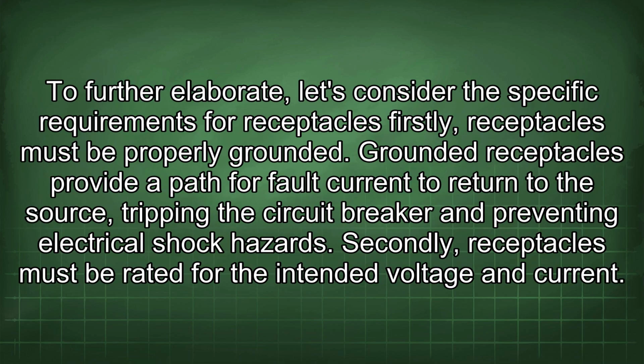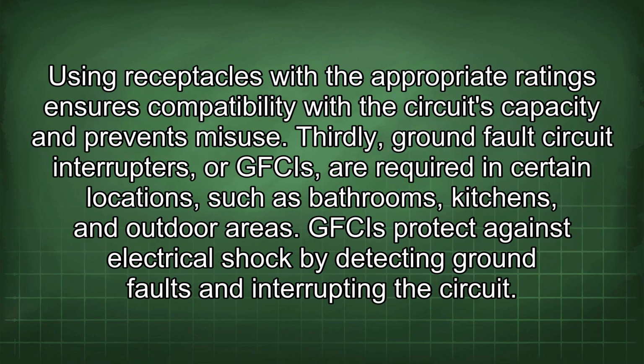To further elaborate, let's consider the specific requirements for receptacles. Firstly, receptacles must be properly grounded. Grounded receptacles provide a path for fault current to return to the source, tripping the circuit breaker and preventing electrical shock hazards. Secondly, receptacles must be rated for the intended voltage and current. Using receptacles with the appropriate ratings ensures compatibility with the circuit's capacity and prevents misuse. Thirdly, ground fault circuit interrupters, or GFCIs, are required in certain locations, such as bathrooms, kitchens, and outdoor areas. GFCIs protect against electrical shock by detecting ground faults and interrupting the circuit.